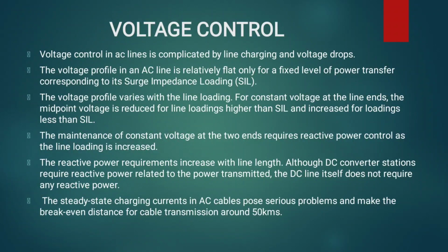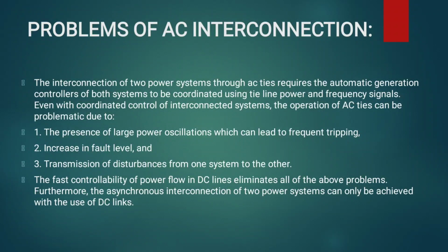The reactive power requirement increases with the line length, although DC converter stations require reactive power related to the power transmitted. The steady state charging current in AC cables poses a serious problem and makes the break-even distance for cable transmission around 50 kilometers. The next one is the problem of AC interconnection.